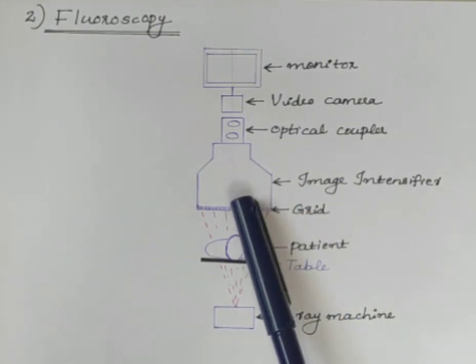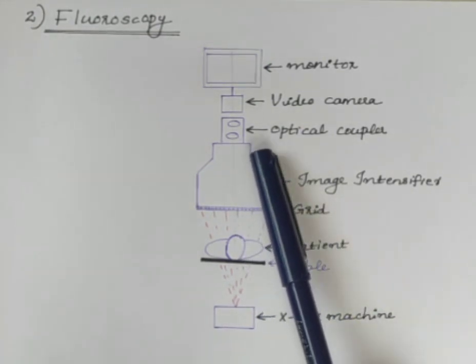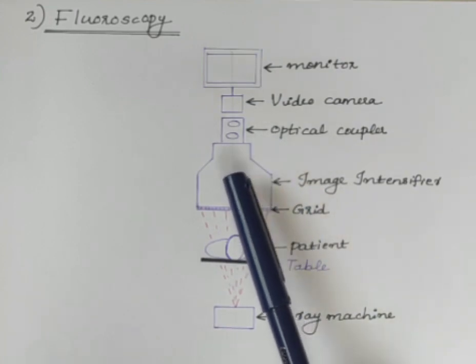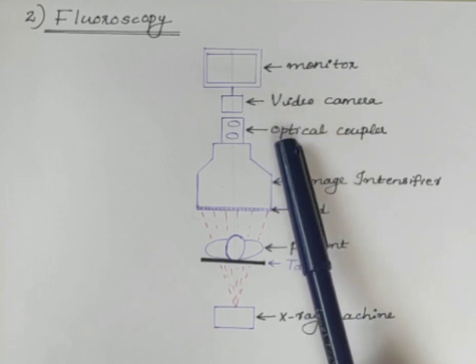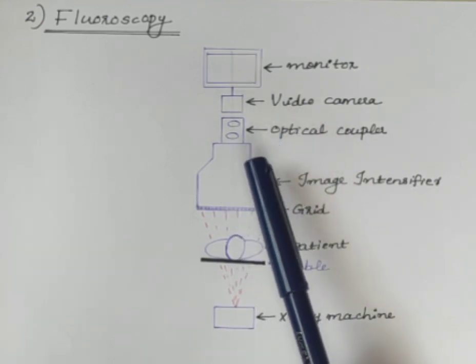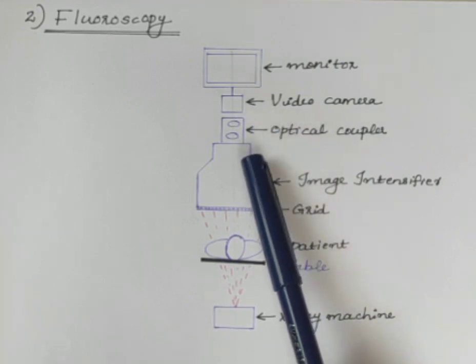The optical coupling is used to couple image intensifier and video camera. So it provides an isolation between image intensifier and video camera.